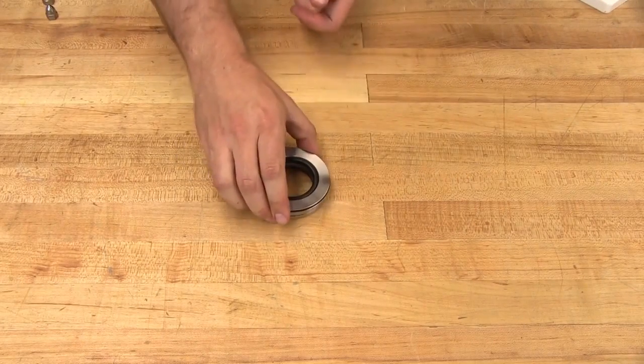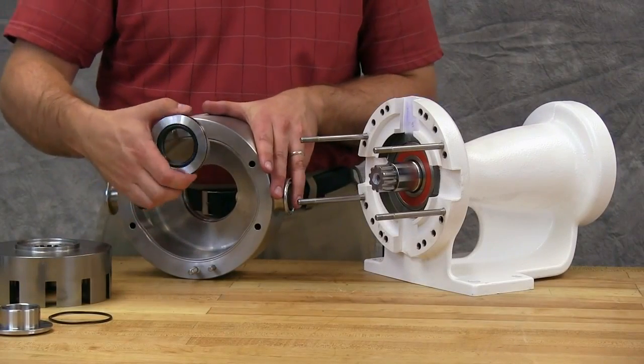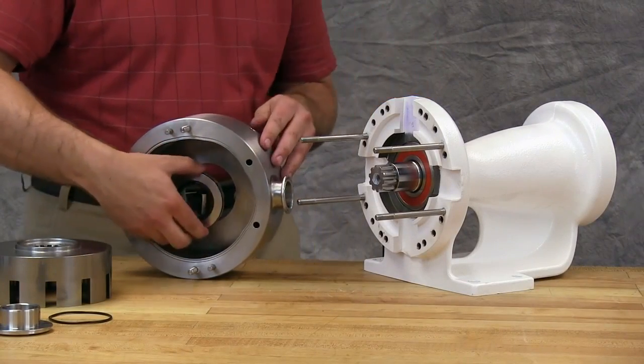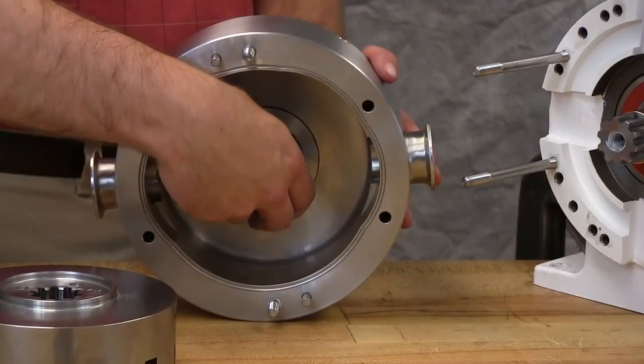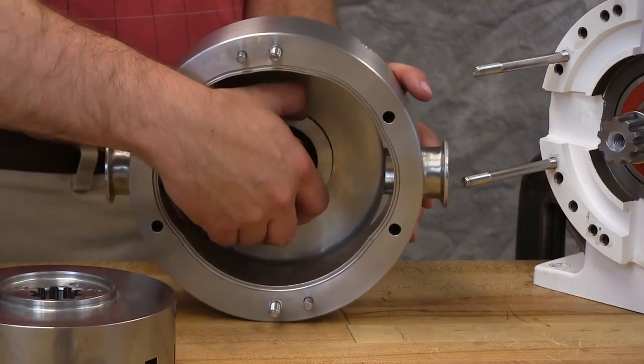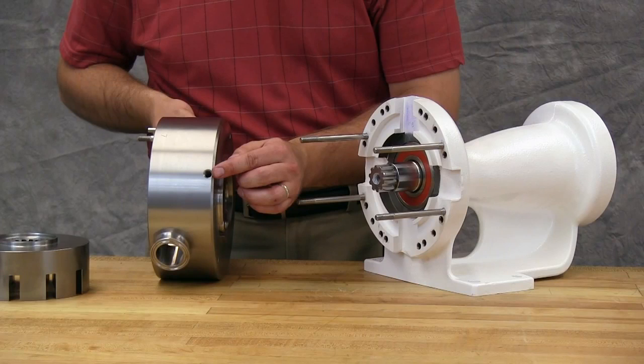Once the seal housing O-rings have been installed, insert the seal housing into the casing. Make sure that the anti-rotation cutout of the seal housing lines up with the anti-rotation washer on the backside of the casing. Pumps with double O-ring seals require barrier fluid. Operating a pump with a double O-ring seal without barrier fluid will damage the seal and pump parts. Follow the barrier fluid recommendations listed in the technical service manual.